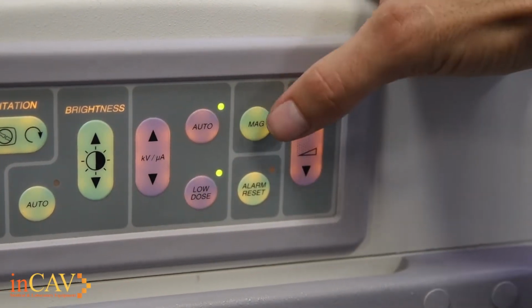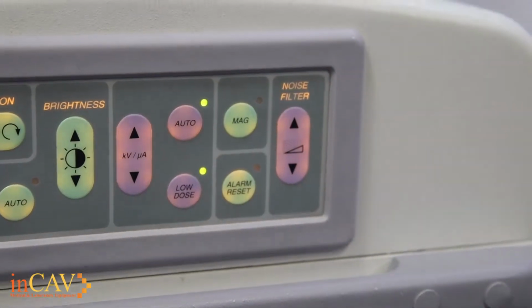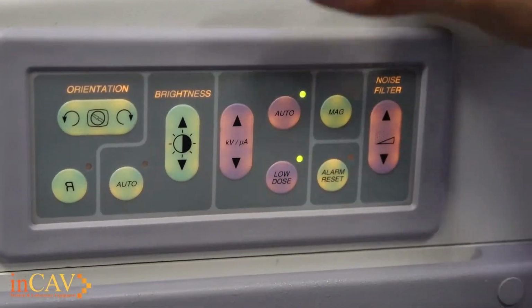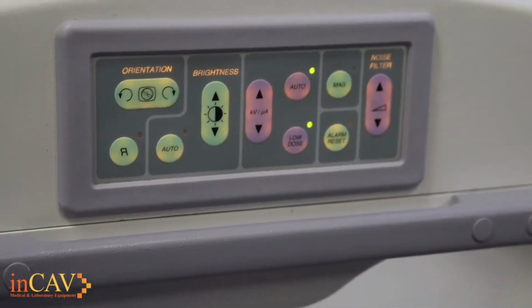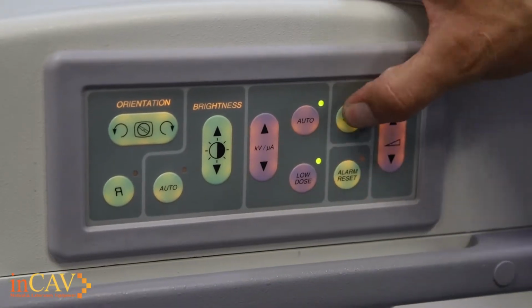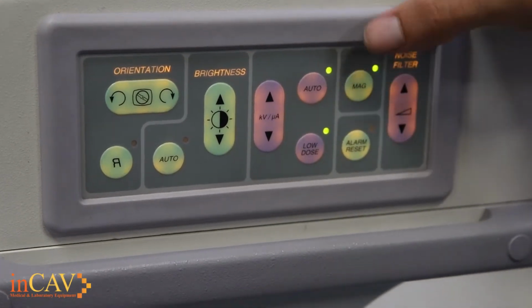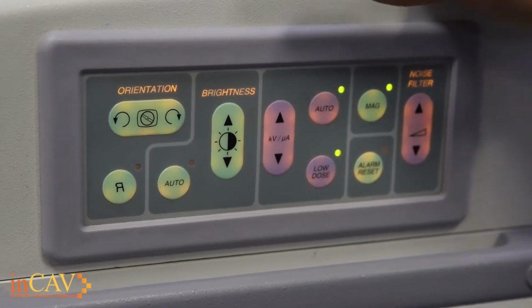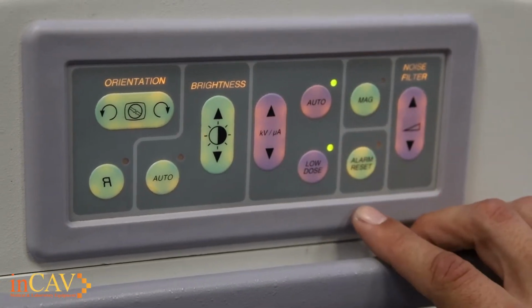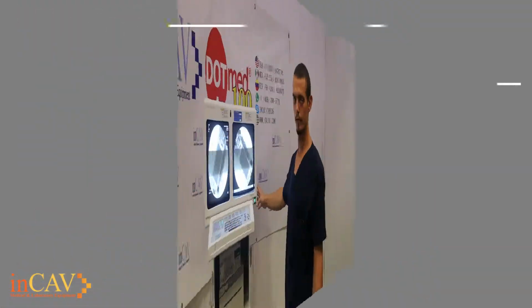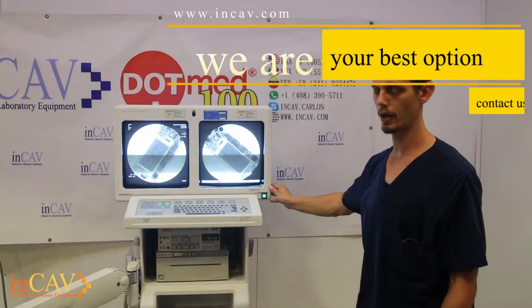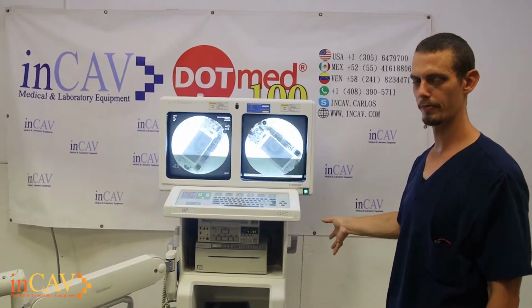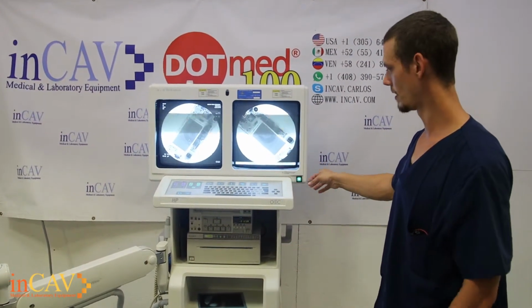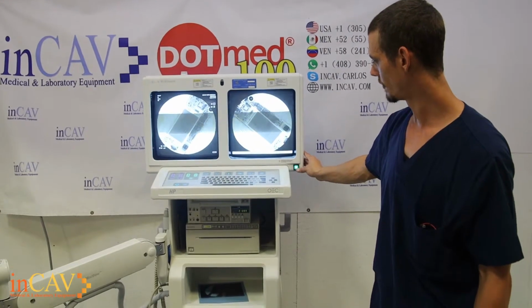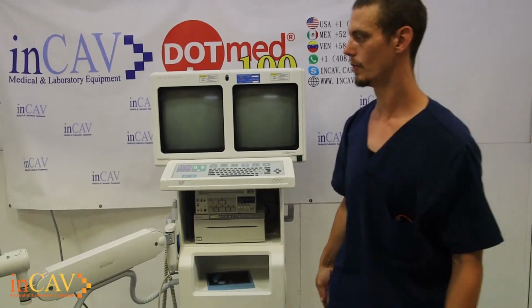And then over here we have magnify. This is different from what you get on the screen. However, this magnification is going to take place in the collimator itself. It'll actually adjust to get a closer view, more precise in terms of whatever it is that you're looking for. So you hit the magnify and your image will be magnified from the actual shot that you get from the machine. Alarm reset, of course, and then your noise filter. Now, very simple. Once you've finished with the procedure, I always recommend to return it to an off position with everything located where it needs to be to start a new procedure. All you have to do is hit the power button, and then we'll go over here.